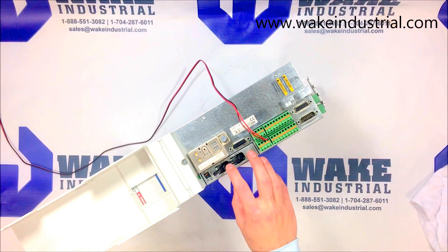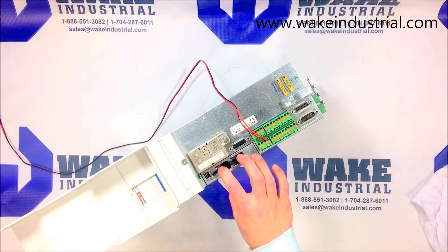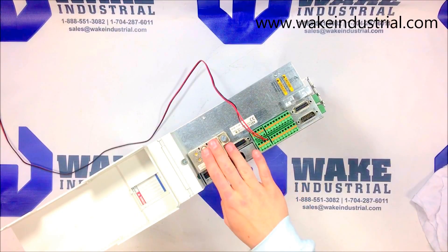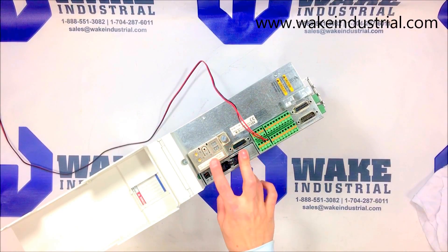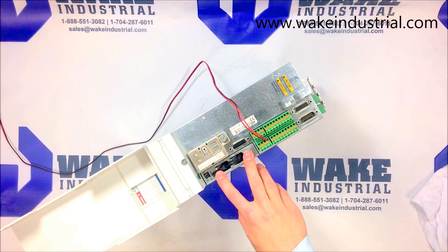Right here you can see the 02.3 option card. The 02.3 option card has Sin/Cos interface capabilities. It is matched with an encoder which are commonly silver to whitish in color. They are usually an inch and a half to two inches long, screwed in with a single screw found right here on top next to the option card.